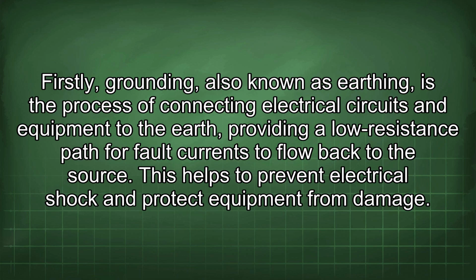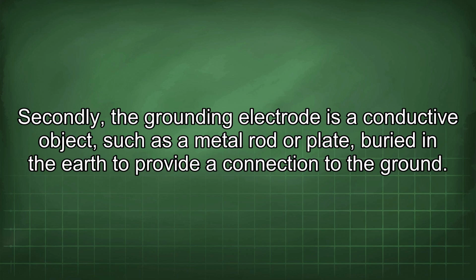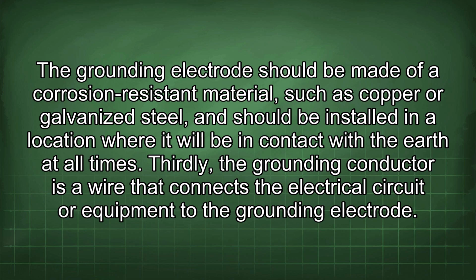Firstly, grounding, also known as earthing, is the process of connecting electrical circuits and equipment to the earth, providing a low-resistance path for fault currents to flow back to the source. This helps to prevent electrical shock and protect equipment from damage. Secondly, the grounding electrode is a conductive object, such as a metal plate, buried in the earth to provide a connection to the ground. The grounding electrode should be made of a corrosion-resistant material, such as copper or galvanized steel, and should be installed in a location where it will be in contact with the earth at all times.